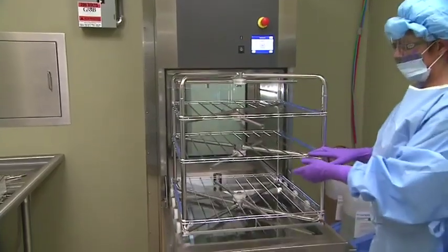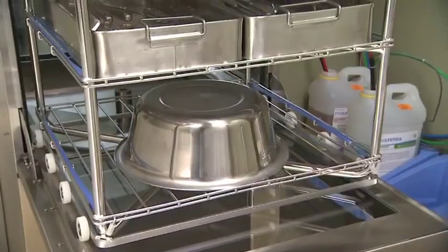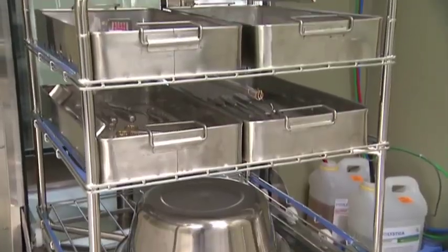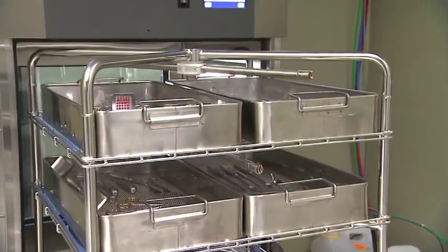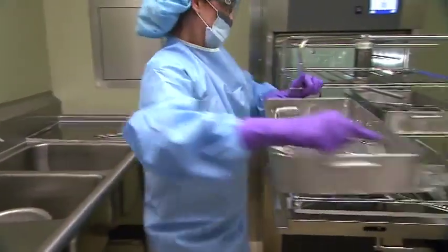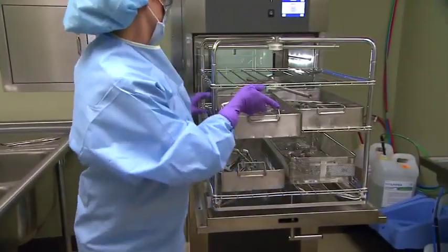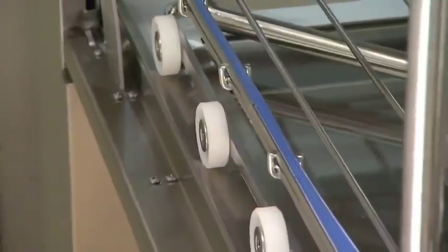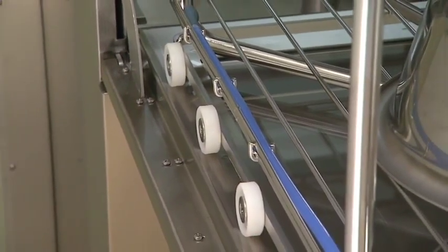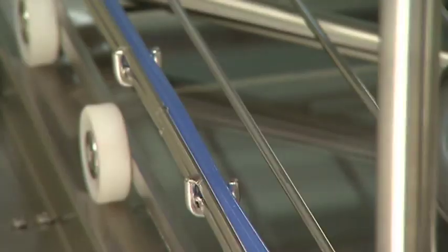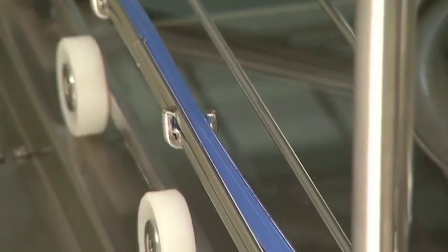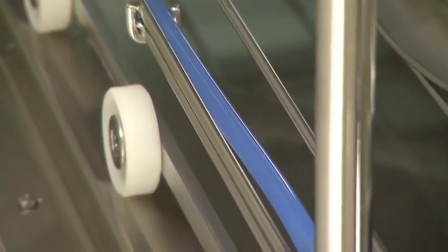The 3-level manifold rack, seen here, is designed to hold general surgical instruments, non-invasive medical devices, utensils, and other similar articles. Each level can hold up to 2 trays. The rack comes standard with easy load wheels and 6 flexible hoses. Each flexible hose is connected to irrigation ports to allow processing of cannulated instruments.